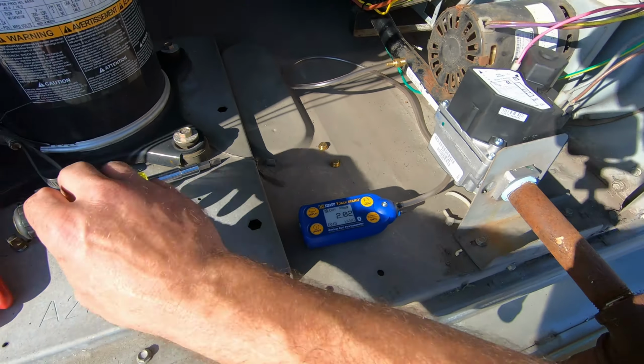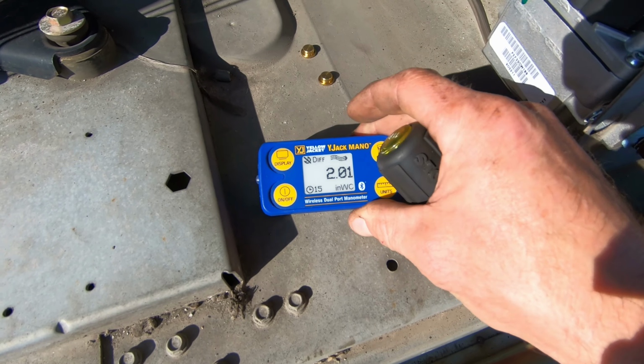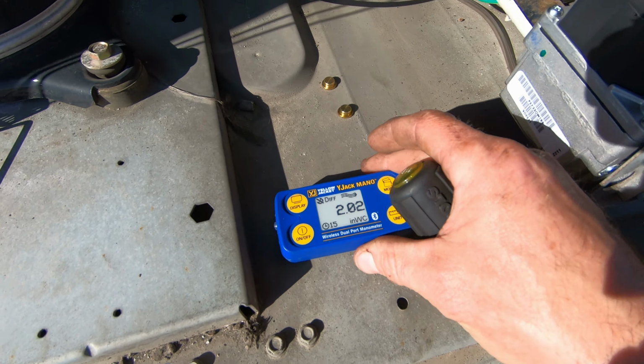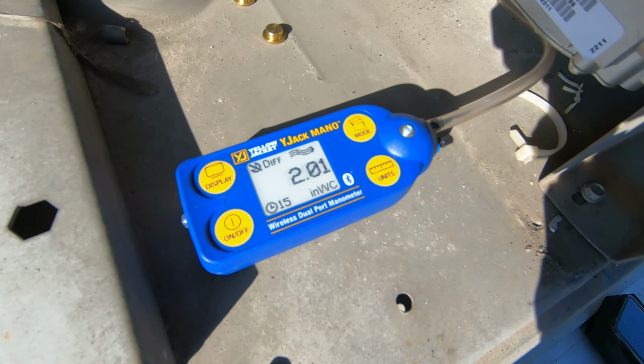I've got W1 jumped out, so we're gonna check gas pressure here, and here we go. All right, there we go. We're running a little high on just first stage. We're at 2.02, so I'm gonna back that down to 1.7.